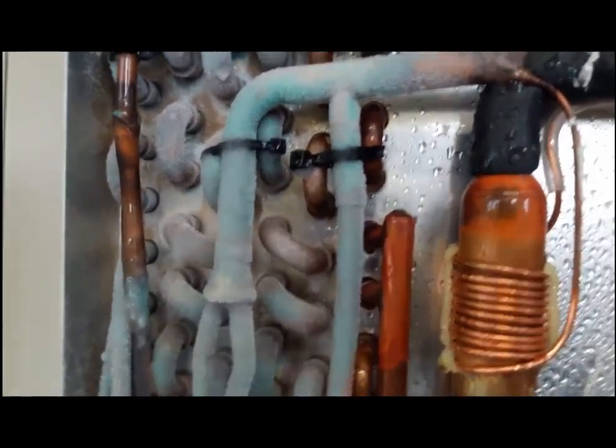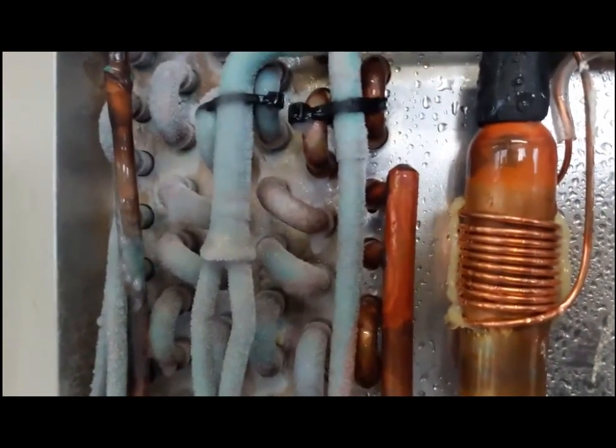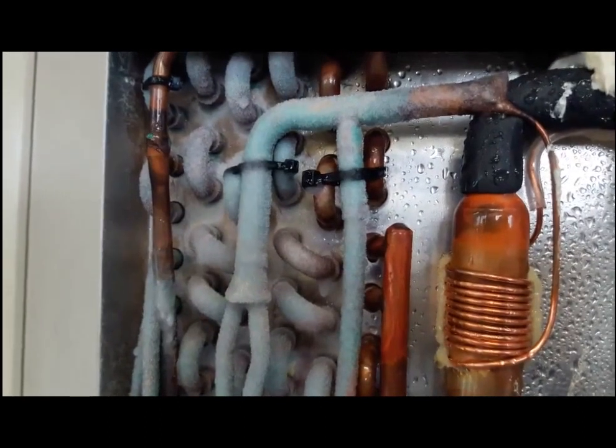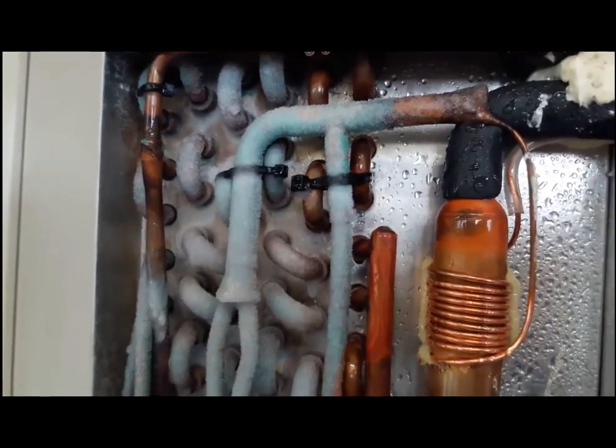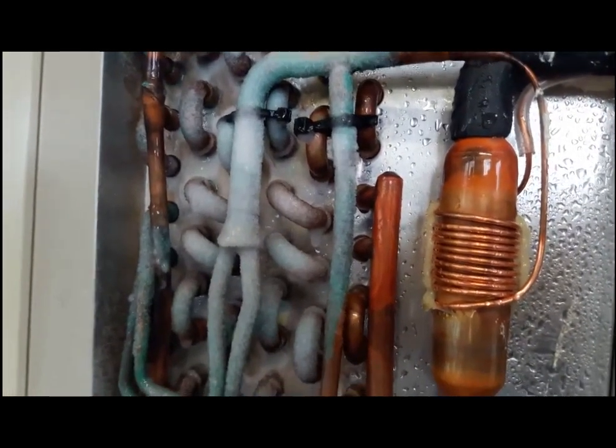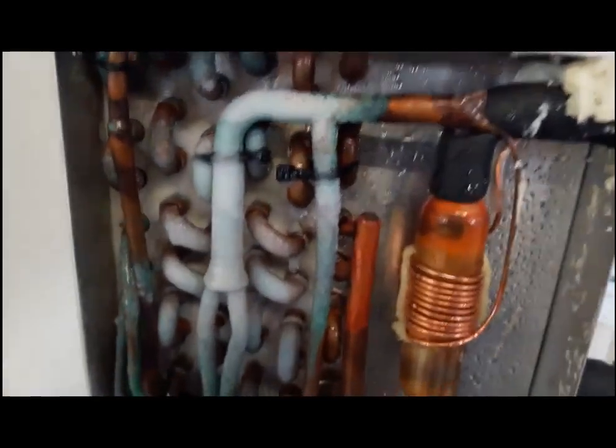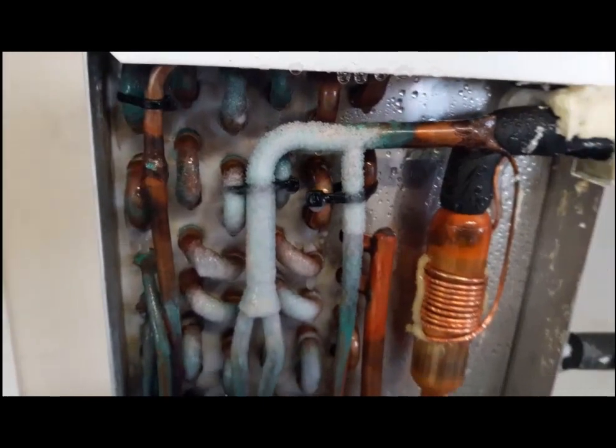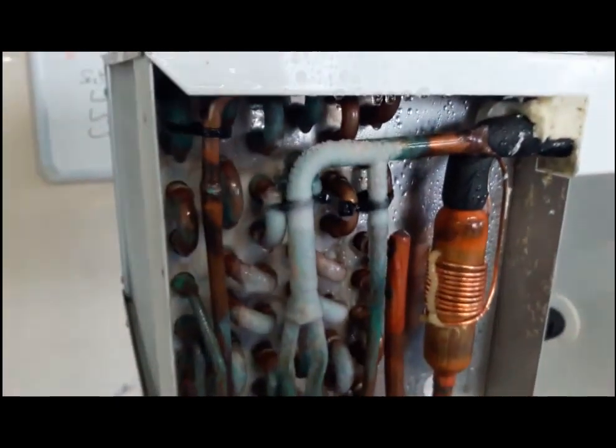Here we can see that the hot gas valve coming from the compressor is open, allowing the injection of hot gas directly into the evaporator. The evaporator begins to defrost. We start to see the frost defrosting very slowly.